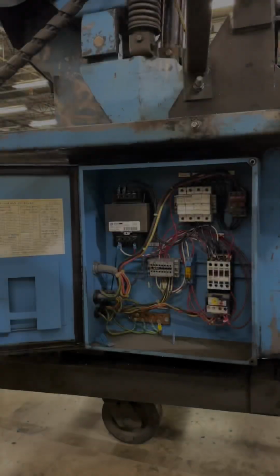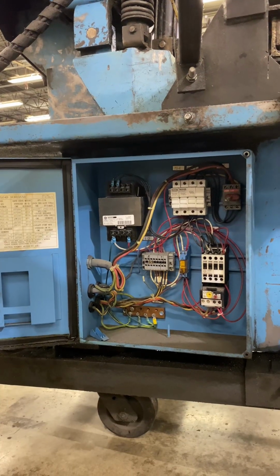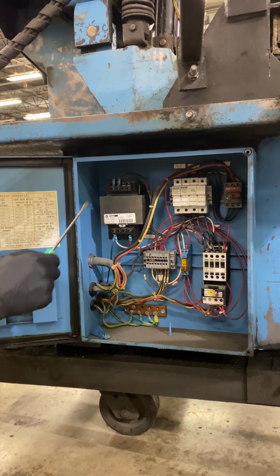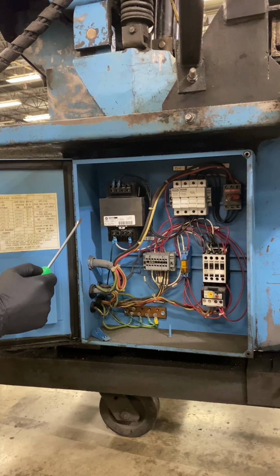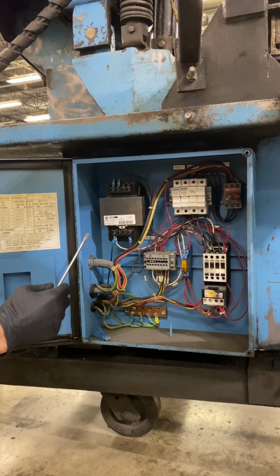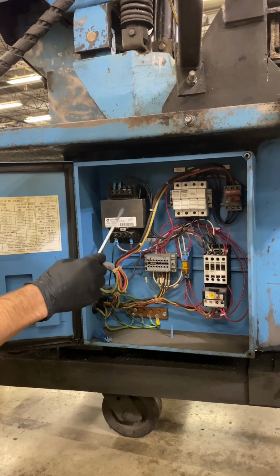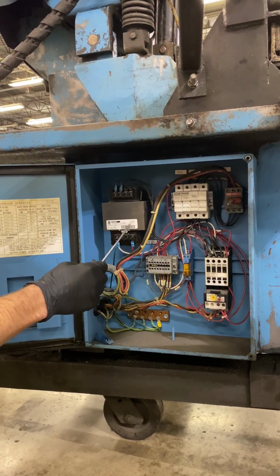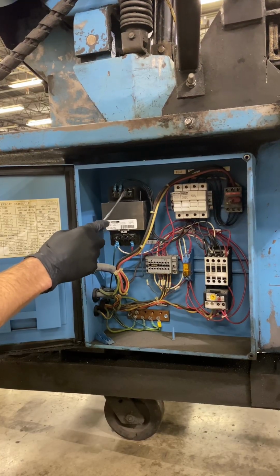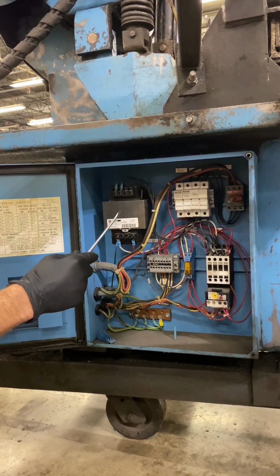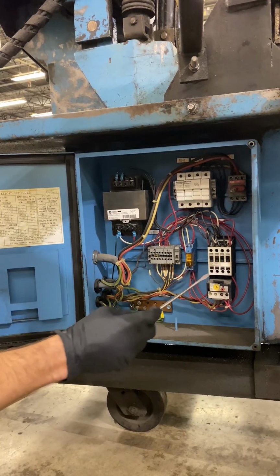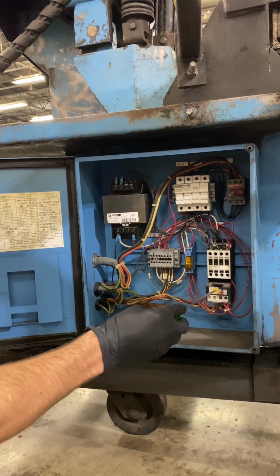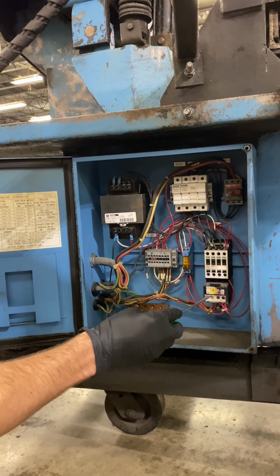So the first thing I'm going to do is look at my transformer, and I'm going to find the taps that are necessary for a 480 volt machine. Right now we're configured H1 to H2, which is 240 volts. What I'm going to do is take H2, move it over to H3, which is going to be our 480 volt input.